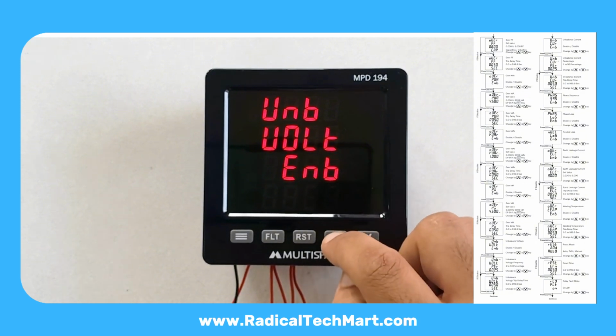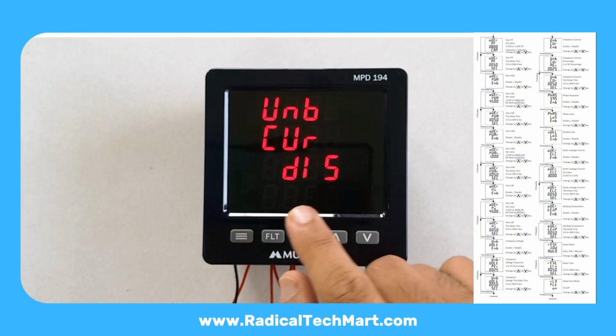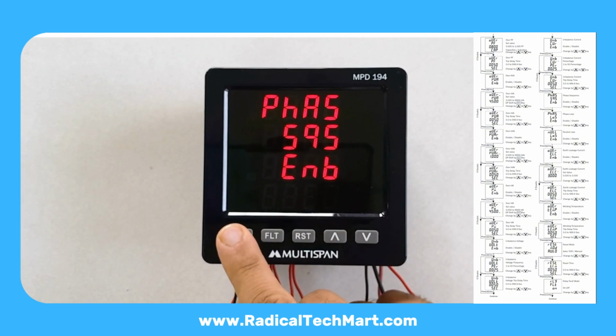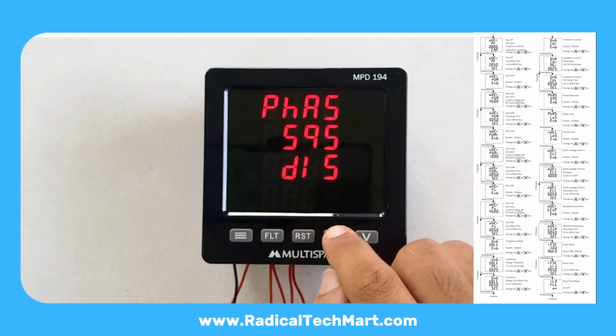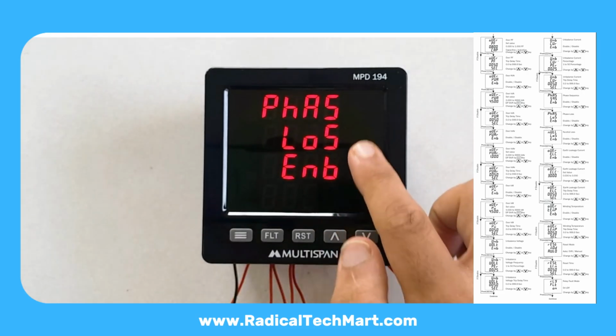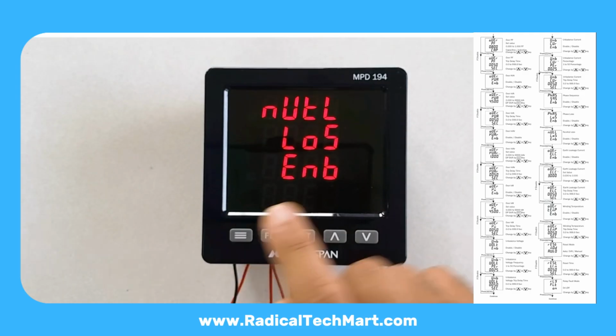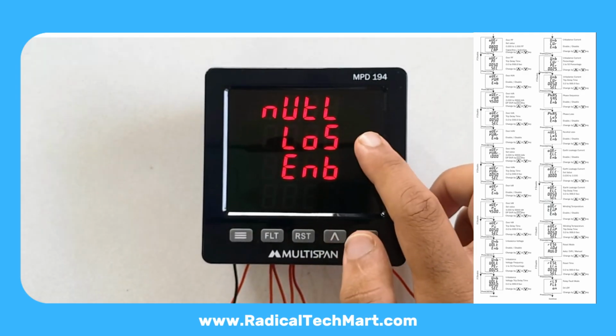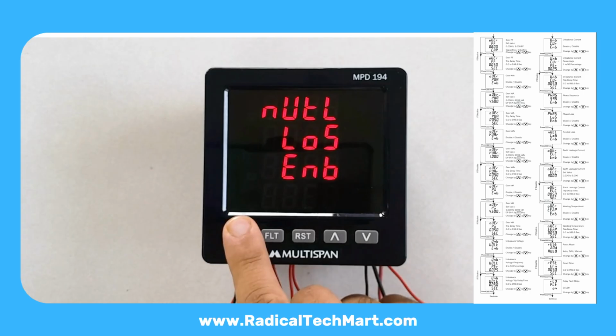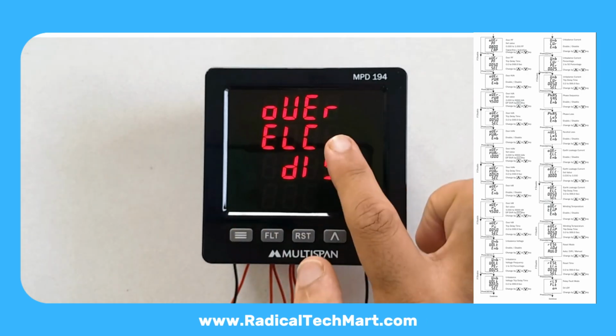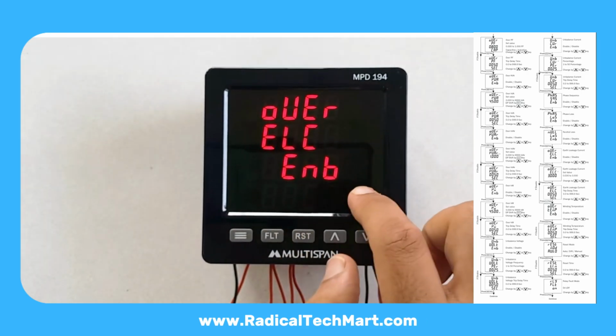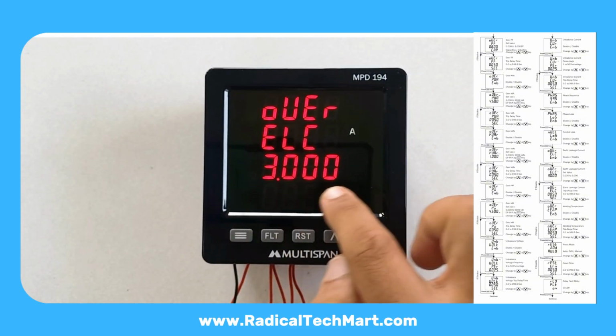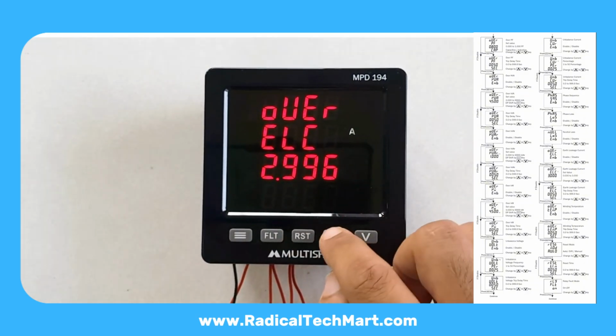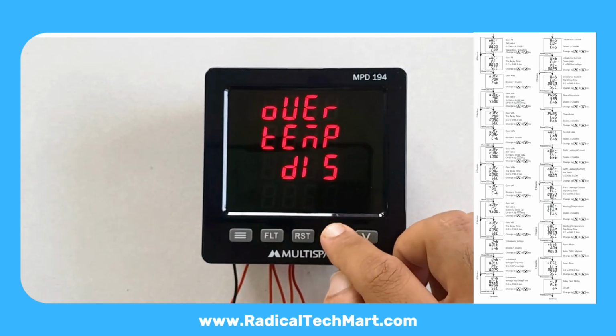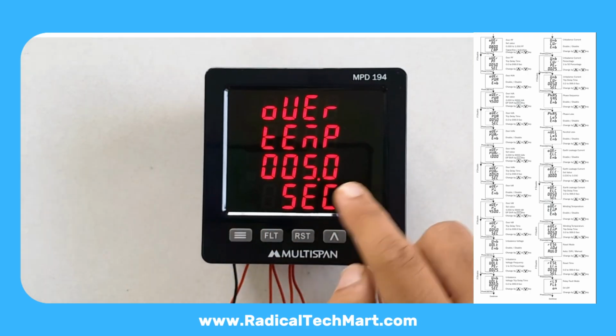Unbalanced voltage, enable, disable. Unbalanced current, enable, disable. Phase sequence, enable, disable. Phase loss, enable, disable. Neutral loss, enable, disable. Enable earth leakage. Set earth leakage current threshold. Set earth leakage trip delay. Enable overtemperature. Set delay time. If PTC indicates high motor temperature, the relay will trip.